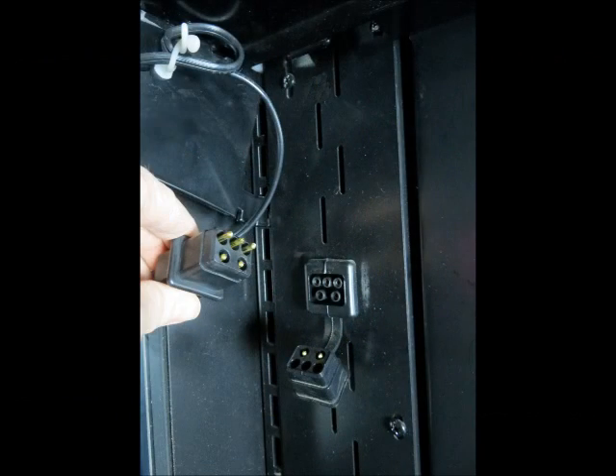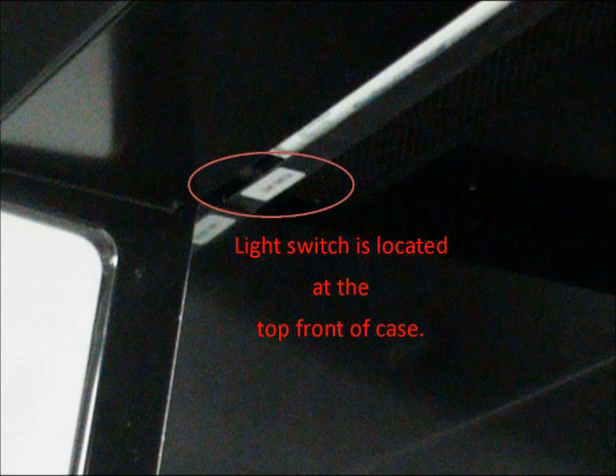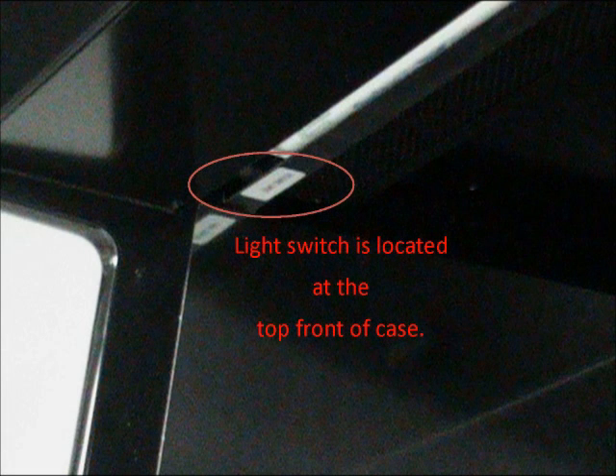The receptacles are located on the back wall of the case. Each light has a five-prong plug that lines up with the receptacle to make the electrical connections. With fluorescent lights, any receptacles that are not being utilized must be capped in order to complete the electrical circuit. The light switch is located at the top front of the case.